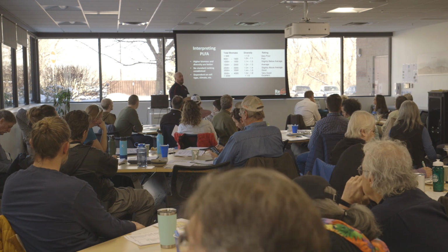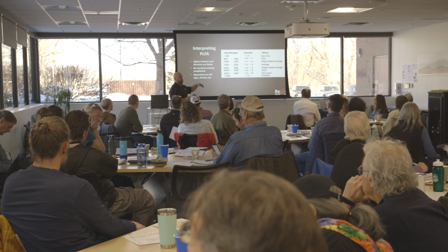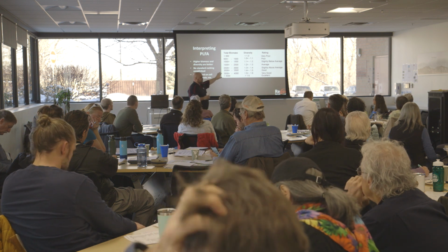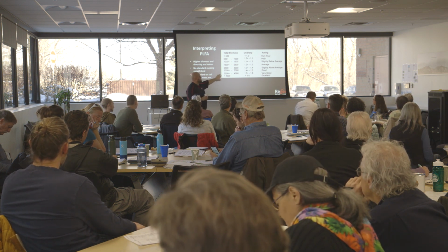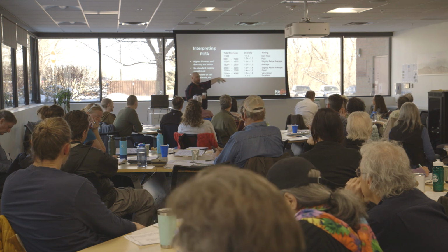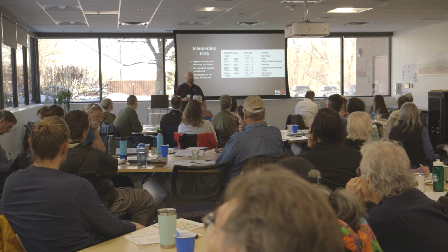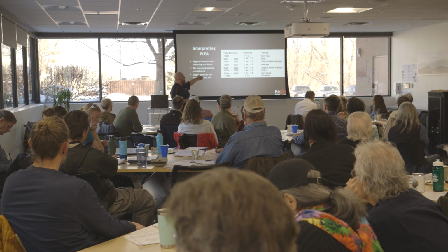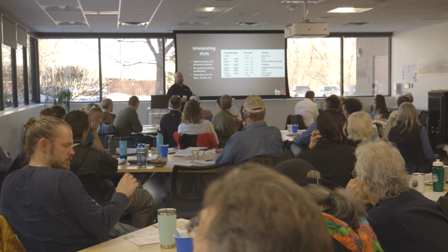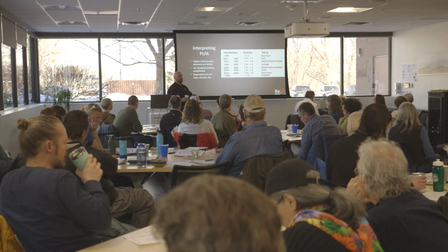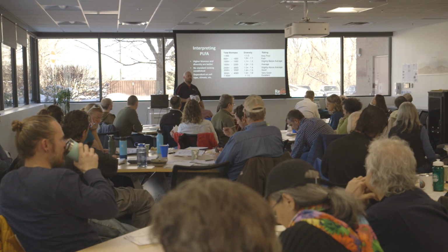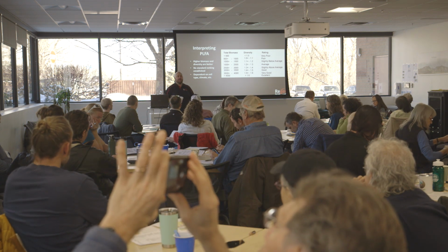This test has been around for decades, but the problem is it hasn't been used commercially. And so what I've done is I've run well over 10,000 of these, and we put together kind of a ranking table. Just looking at what kind of ranges we typically see, what's our average. We did the same thing with diversity. This gives you at least a place to start. And it should be regionally specific, but it's not, because I simply don't have that kind of time and I don't have that kind of data set.